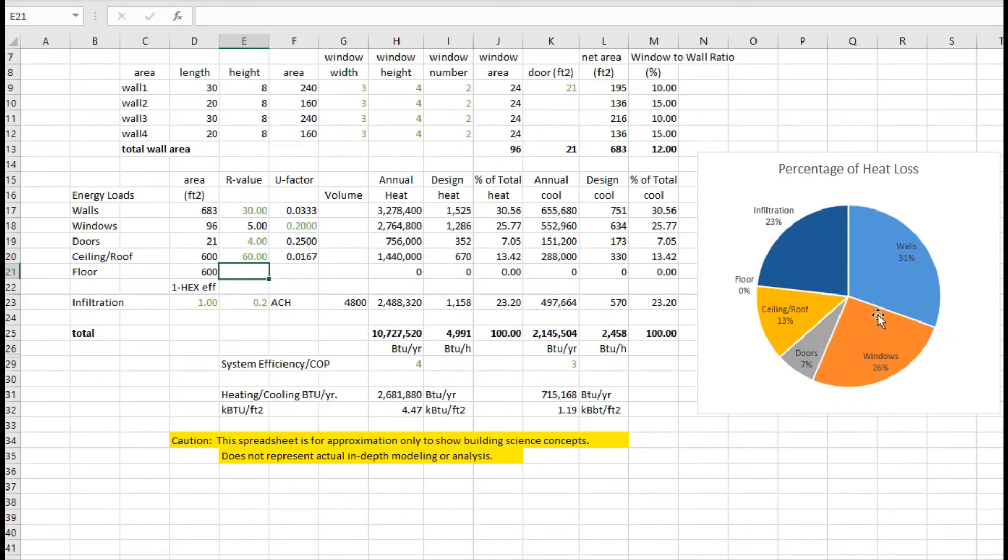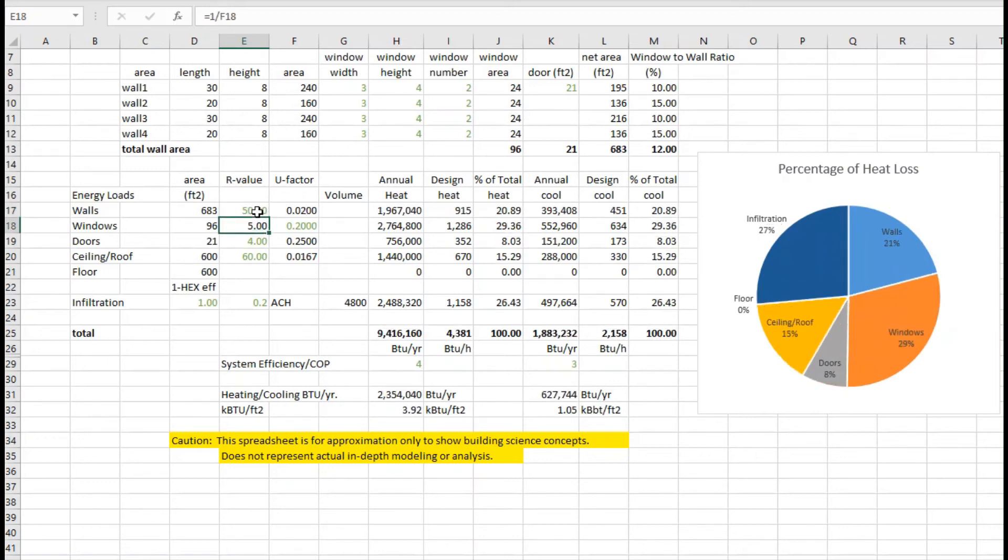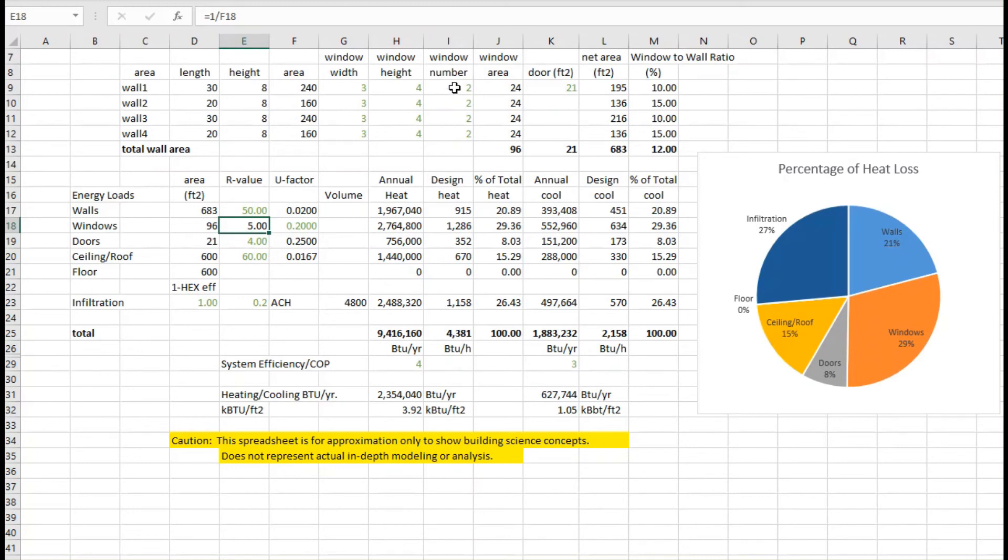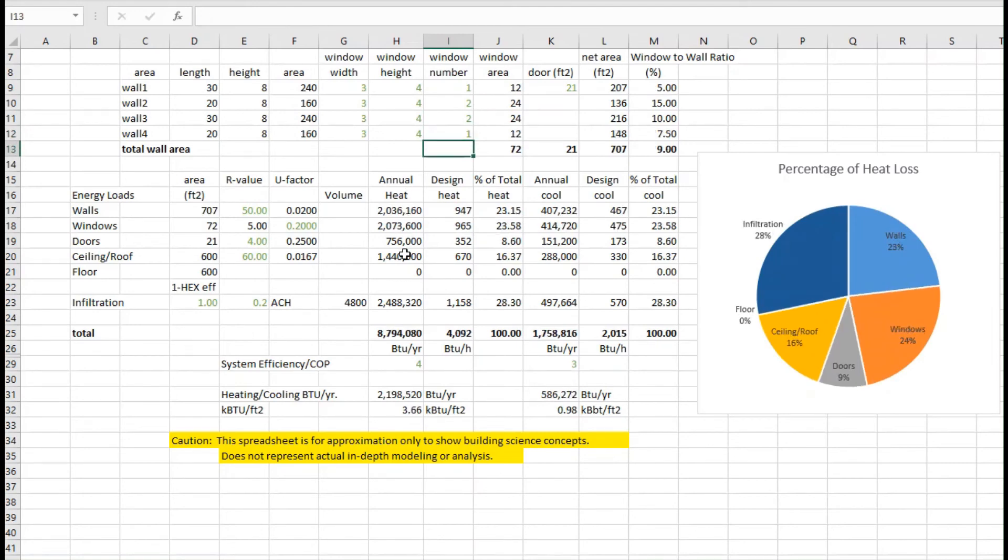Really looking at this, I'm not going to be able to do too much more with the R value of the walls. If I really go to a thickened wall, maybe I could get to R50, but now I've got to deal with special wall considerations. Windows are going to be tough - I can't really reduce the U-factor too much more. But what I could do is continue to reduce the number of windows. Maybe on these smaller sides, I'm only going to put in one window. That will also have an impact.